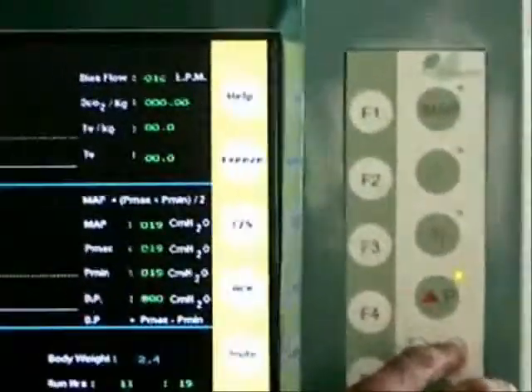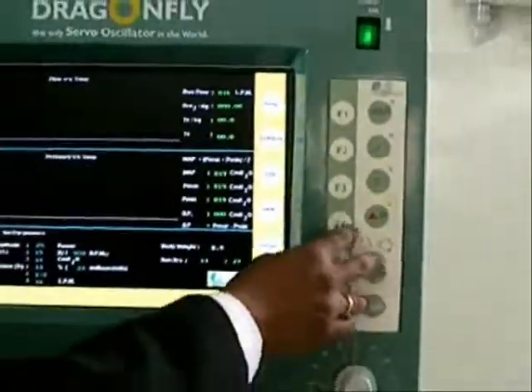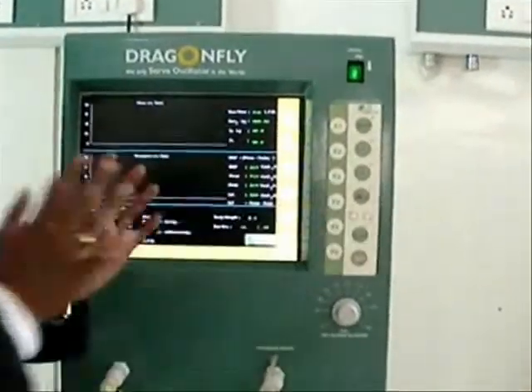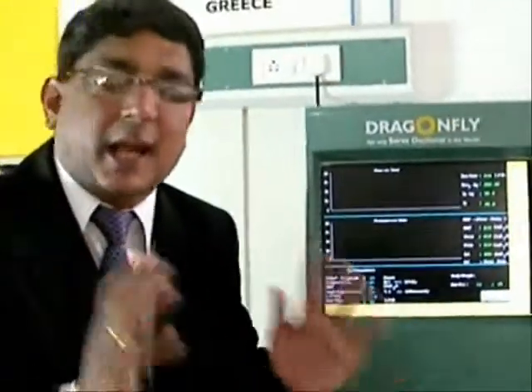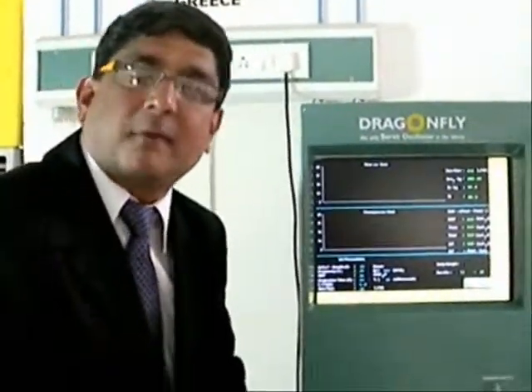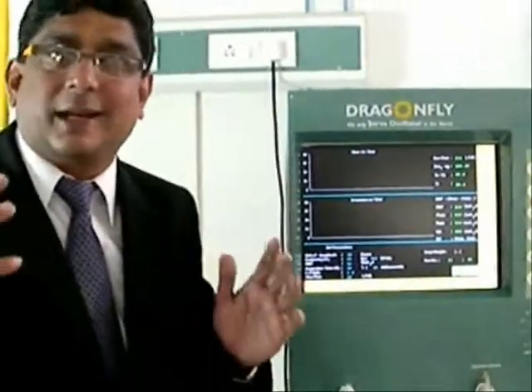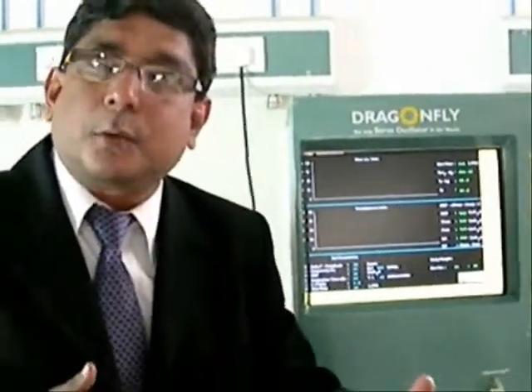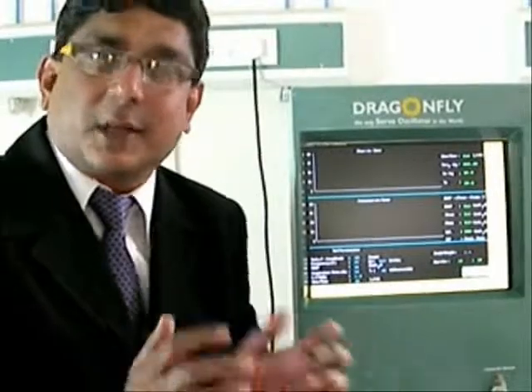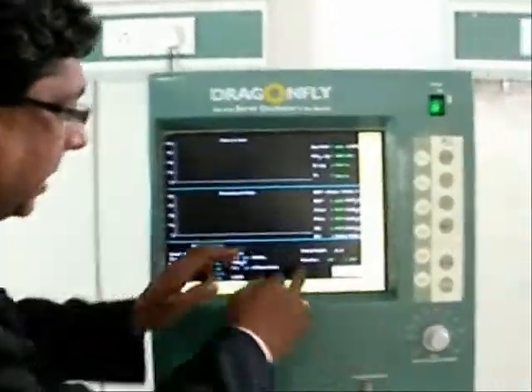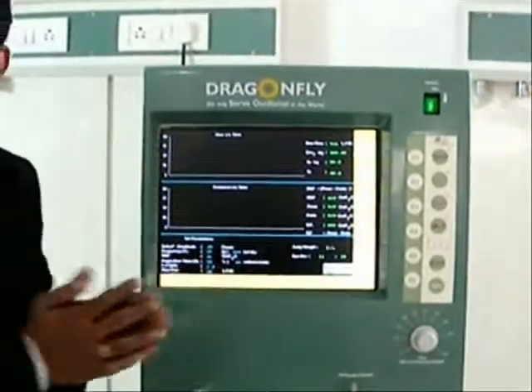Simple. Now I want to set the amplitude or the delta P, the power to the piston. Same thing, press this delta P key, use the up and down keys, press enter. Inspiration time we can set to an I:E ratio of 1:1 or 1:2, or an inspiration time of 33% or 50% of the duty cycle time. What is the duty cycle time? The duty cycle time is the time taken by the piston to move to and fro. Now here you have a feature like body weight.